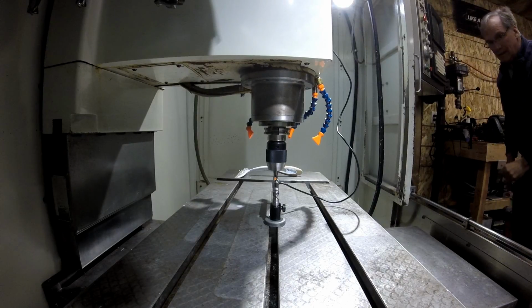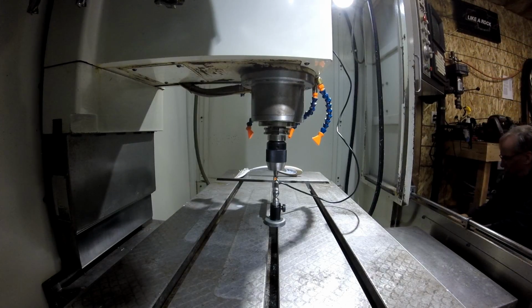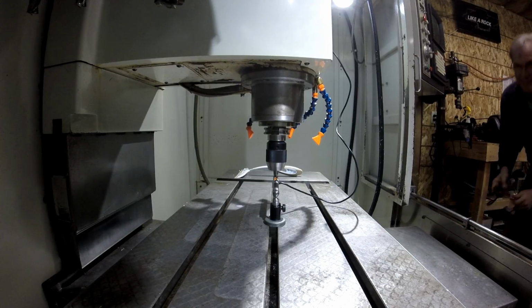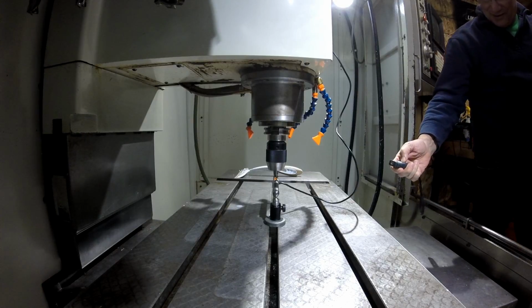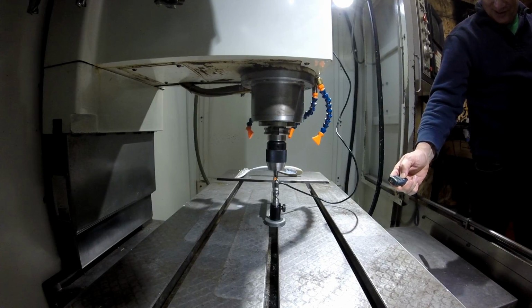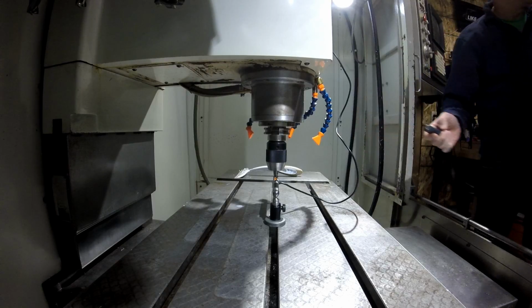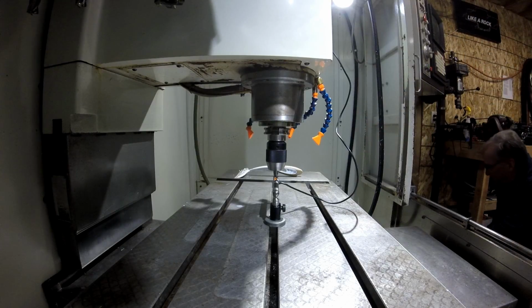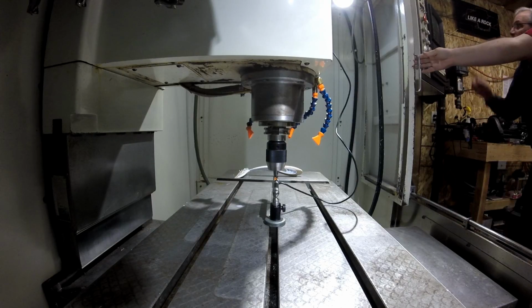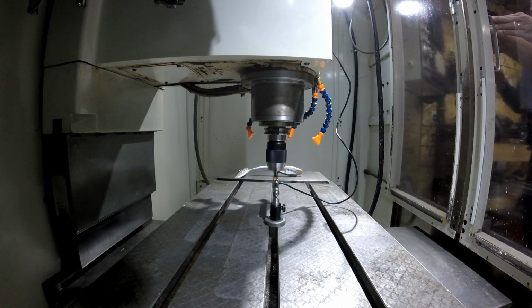Now with the ball bar comes a calibration standard, and that's what Brian was doing. It's basically just a board with balls on it at set distances. So you snap the ball bar on those balls, and then you tell the computer, okay, calibrate it, and it knows what the distance is between those two balls. After you have it calibrated, you snap it in the machine, and Brian's measuring the temperature of the machine, and then the software will compensate back to a reference temperature for you. So you have to tell it what the temperature of the machine is, and then it knows how much temperature compensation to apply.